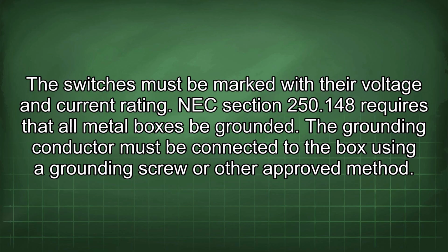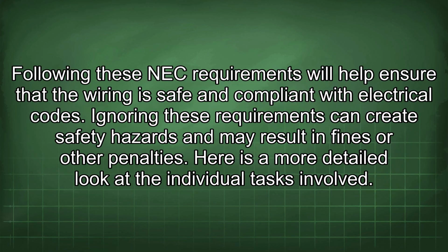NEC Section 250.148 requires that all metal boxes be grounded. The grounding conductor must be connected to the box using a grounding screw or other approved method. Following these NEC requirements will help ensure that the wiring is safe and compliant with electrical codes. Ignoring these requirements can create safety hazards and may result in fines or other penalties. Here is a more detailed look at the individual tasks involved.